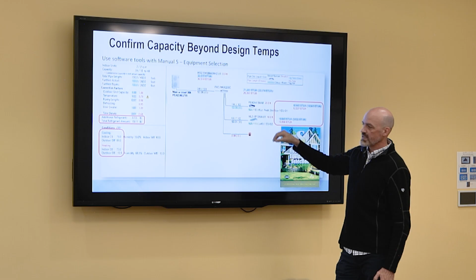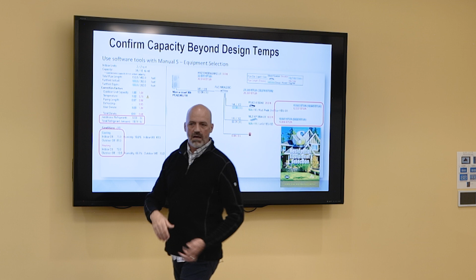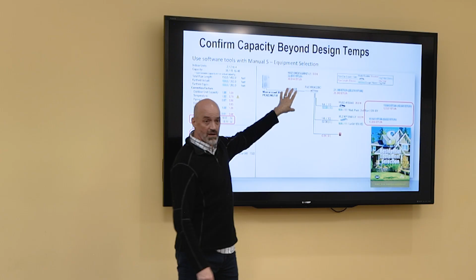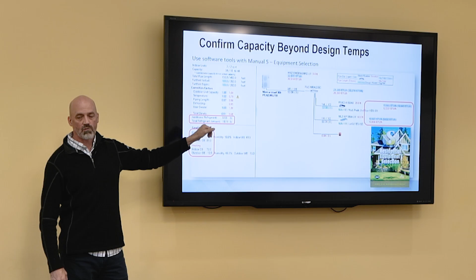This is part of your Manual S selection process, just making sure that 12,500 BTUs is enough to cover that second floor zone, etc. But also in here is the charge of refrigerant. How much additional refrigerant might we need for that system? Well, in this system, the additional refrigerant is 8.53 pounds to run this overall system, basically because this doesn't ship with all the stuff in it. If you've got a one-to-one, like a monoblock, like a hydronic monoblock, which we'll see in a minute, it's going to have all the refrigerant on board. You're not going to have to add anything additional. You're just adding water, or water with glycol or some other antifreeze, into the loop.